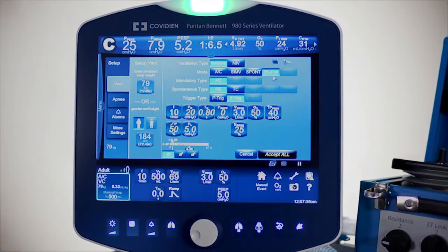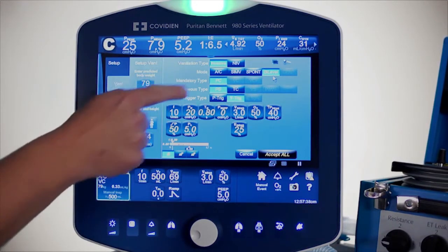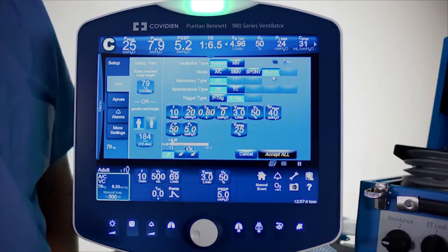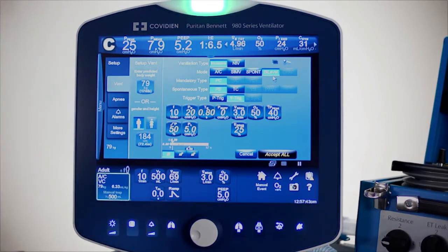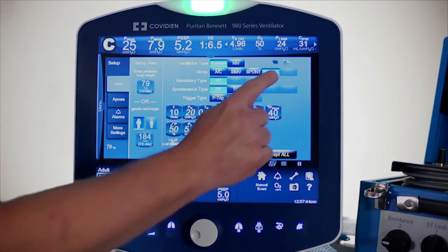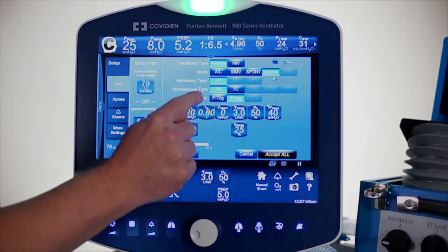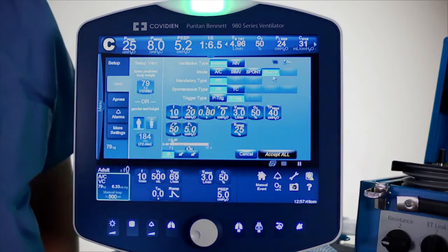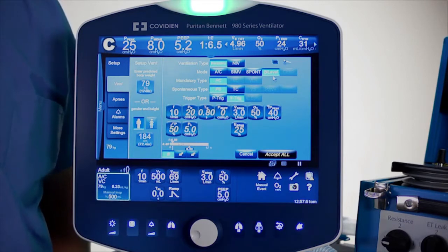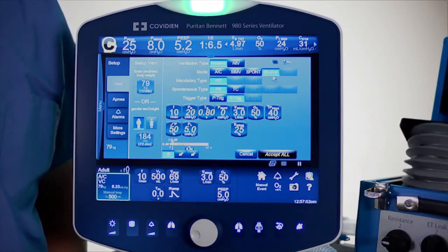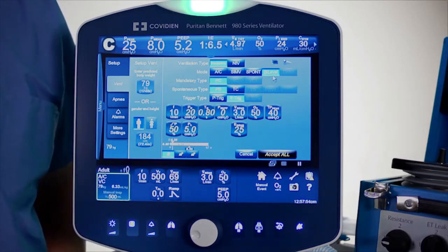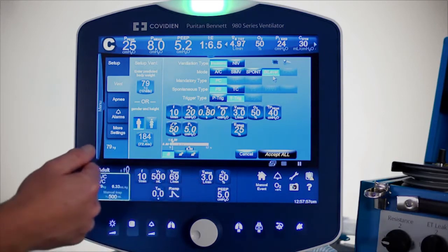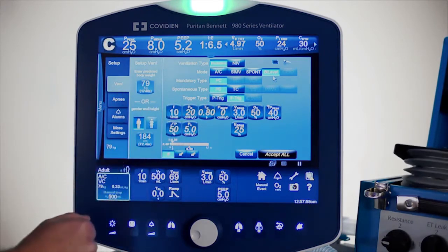The mandatory type is pressure control — there's no option there, so it really is an SIMV pressure control. You can also decide whether to support those spontaneous breaths with either pressure support, tube compensation, or nothing at all. I'll put on some pressure support for now.